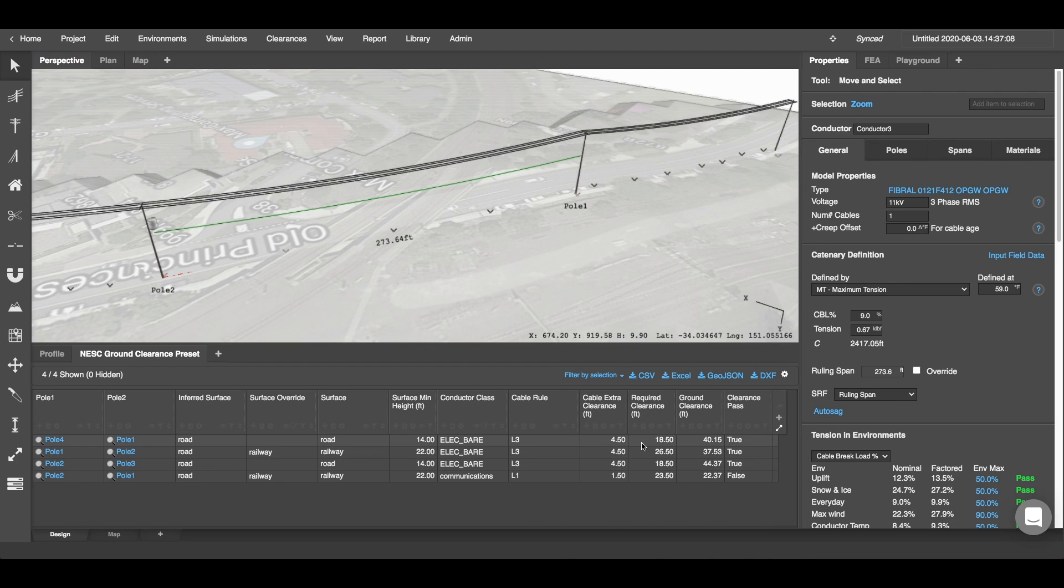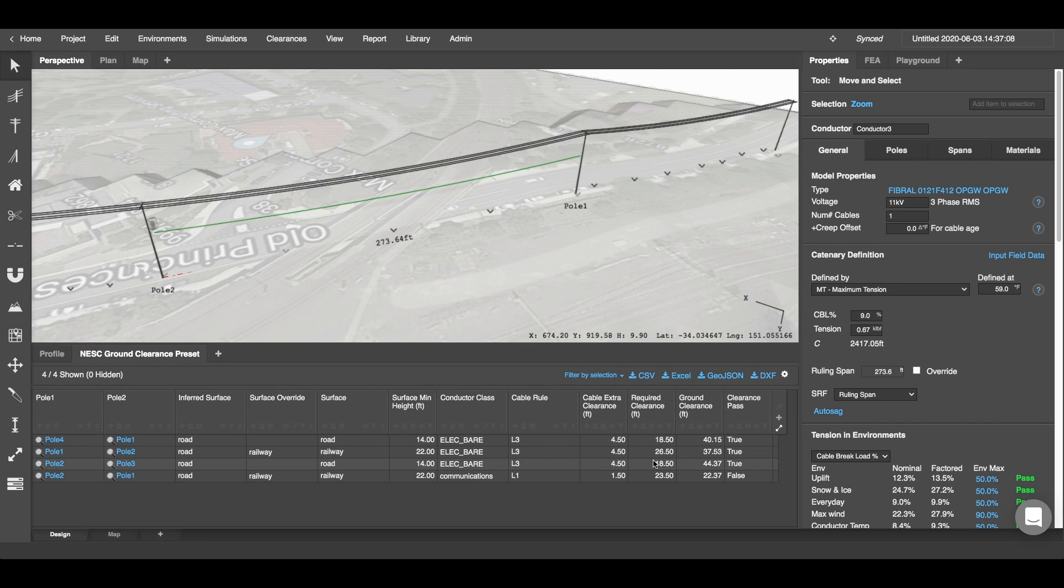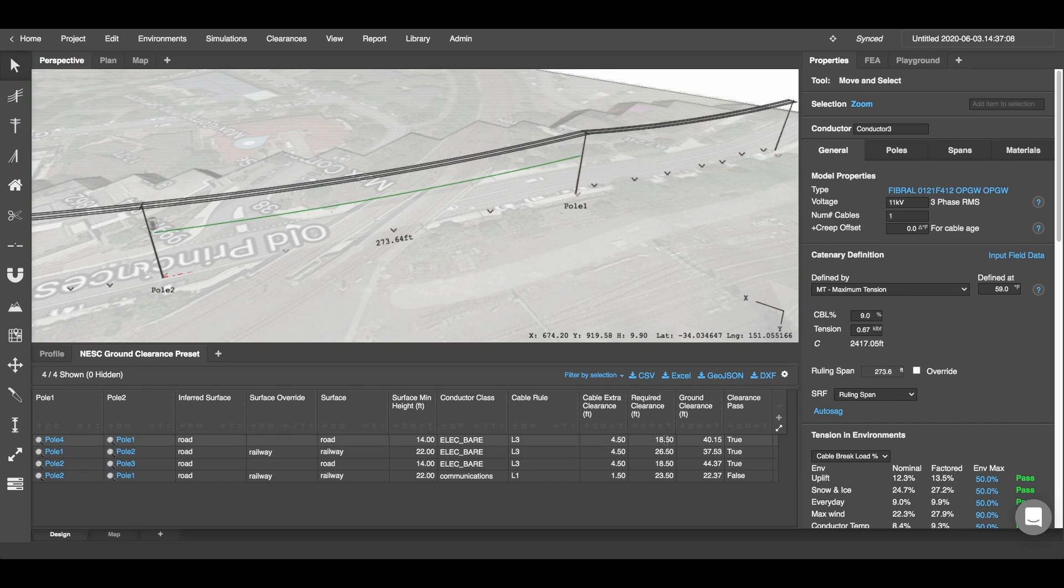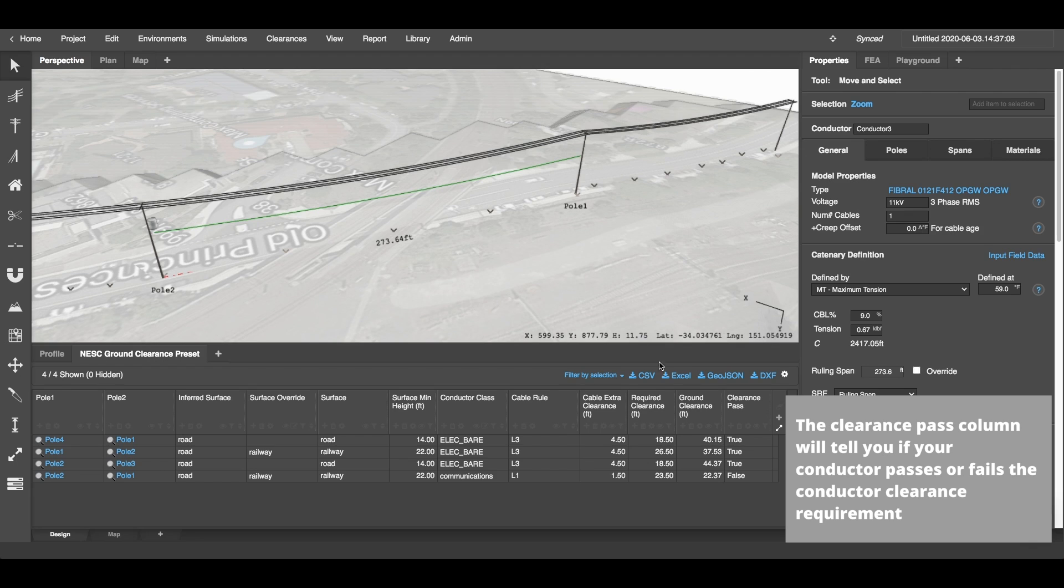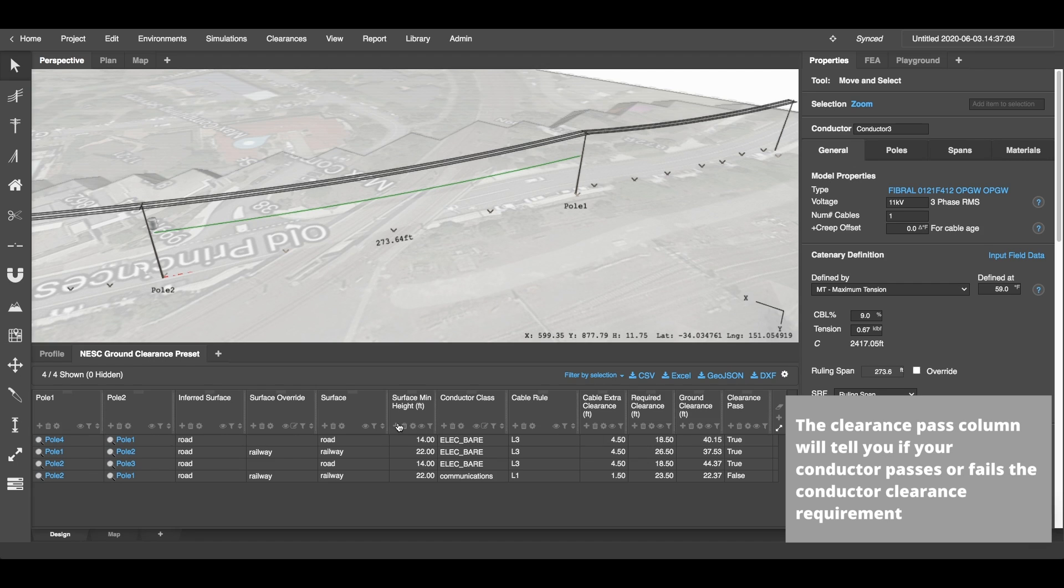Now the next column across is the required clearance column, and this will be the total of cable extra clearance and your surface min height. That will be the overall required clearance measurement that you need between your ground point and your conductor point. And then your ground clearance over here is your actual current measurement.